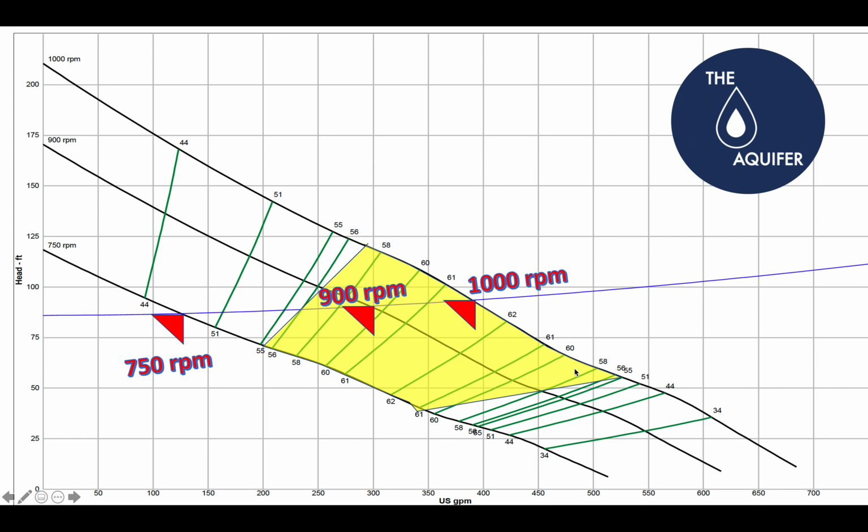So what we're seeing here are the ISO lines for pump efficiency in green. As you move up closer and closer to this best efficiency point, which is probably somewhere right in here, you can see your efficiency lines getting better, and then as you move away, it obviously goes down. So what I've done here is demonstrate our preferred operating range from our pump manufacturer, and this is something like ranging from 70% of best efficiency point up to about 120% of best efficiency point, which is something similar to what you're going to see.